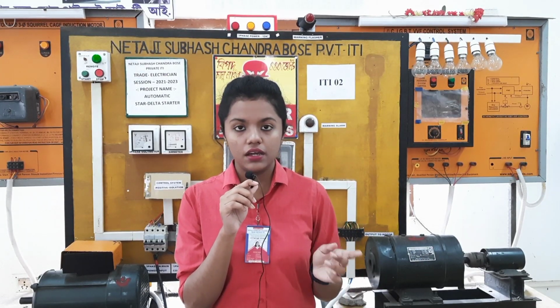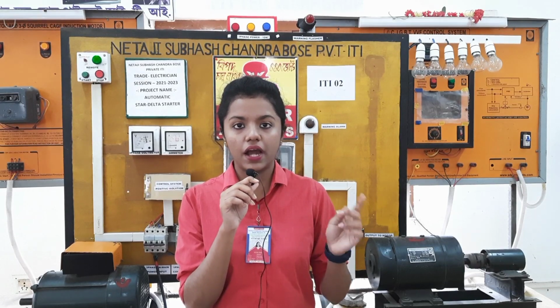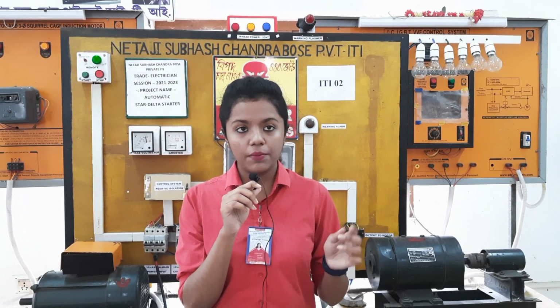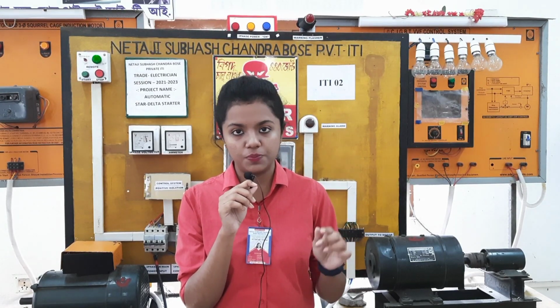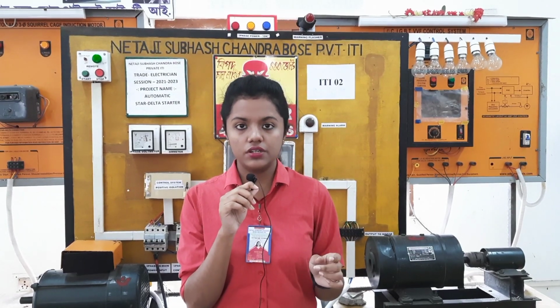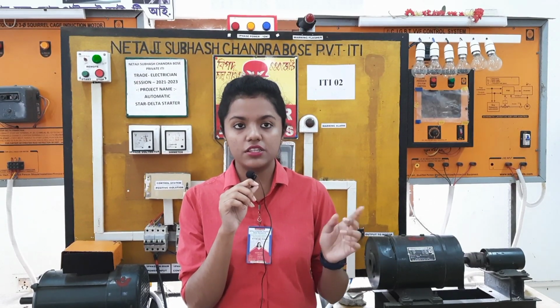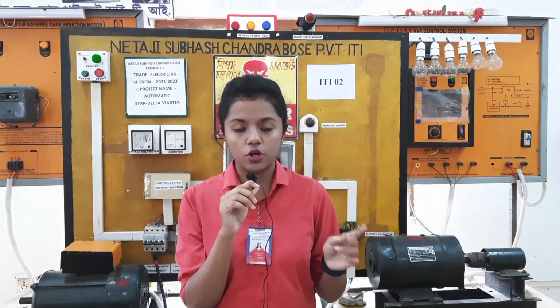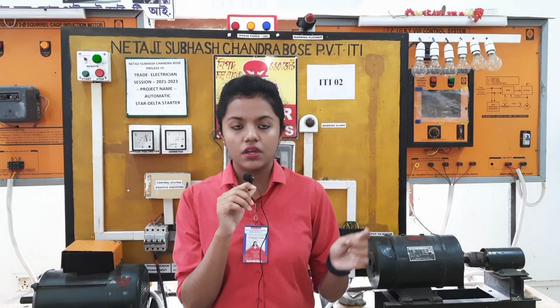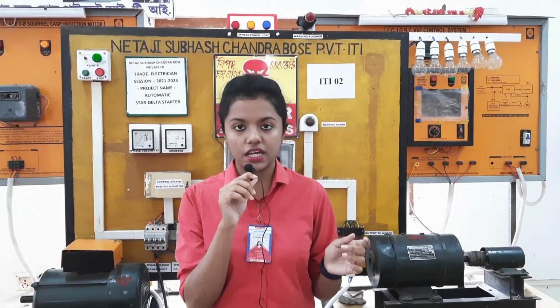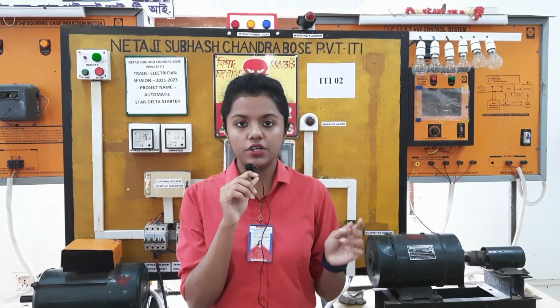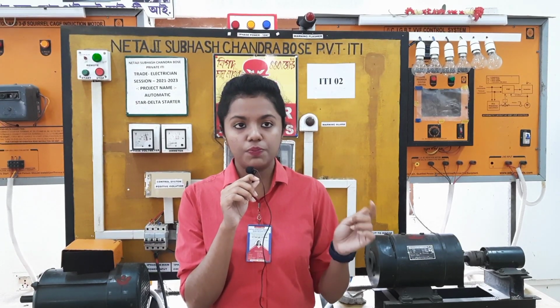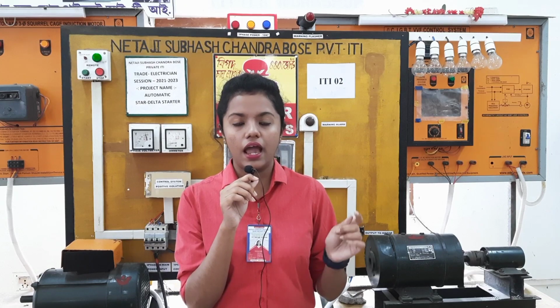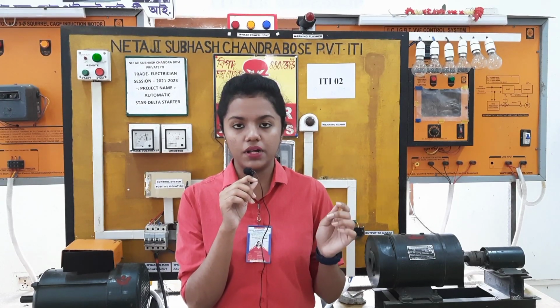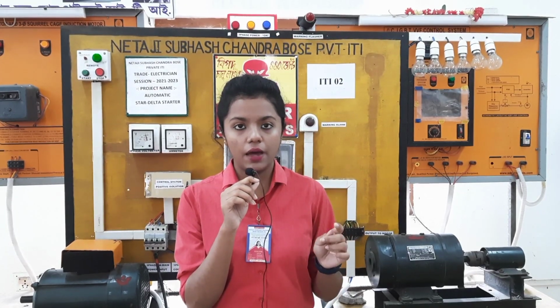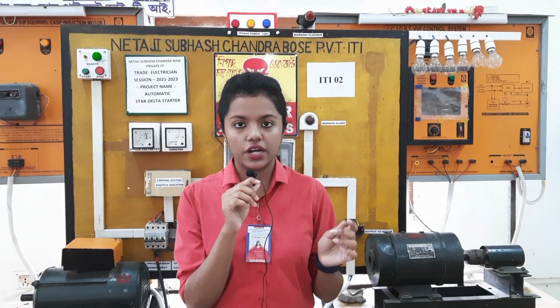After a few seconds, the motor coils become connected in delta at about 75% of rated speed. In that condition, all the three coils get the full voltage and draw more line current. But this time the phase current is 1 by root 3 of line current, which passes through each coil, and the motor runs at normal speed. Here we have made an auto star delta starter.